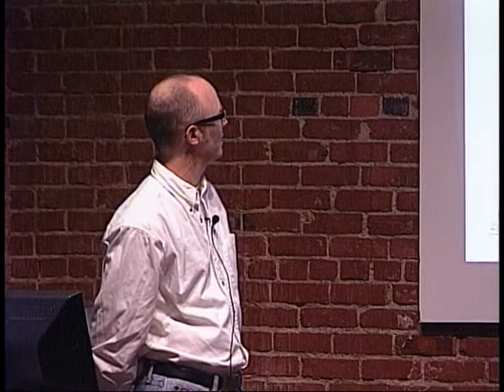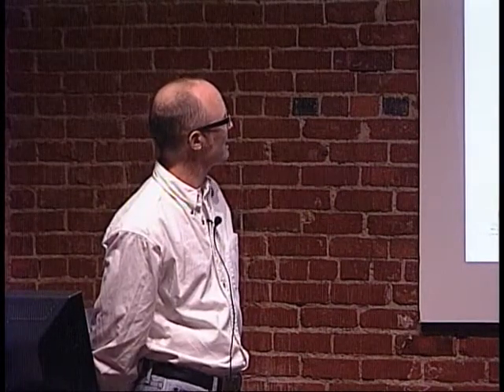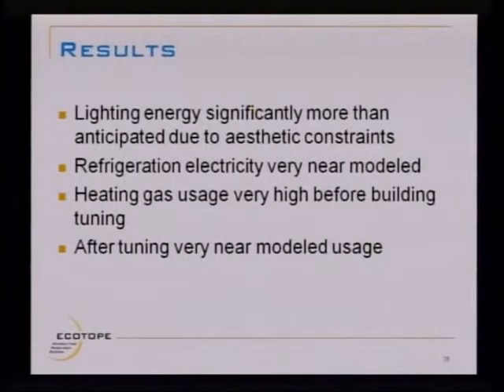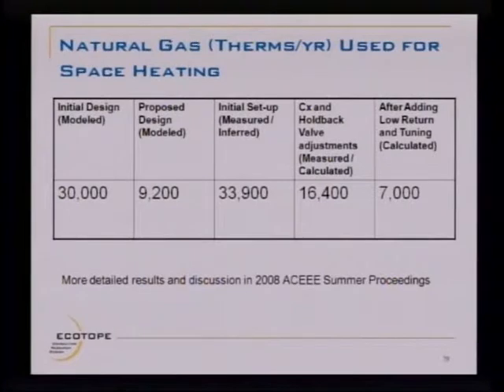The refrigeration electricity was very nearly what we modeled early on, which was somewhat gratifying. It meant that our model wasn't too far off. The gas heating energy was very high initially, reduced quite a bit after commissioning, and then reduced again quite a bit after the building tuning. And after the tuning, it was pretty close to what we'd modeled. This is the natural gas energy usage.